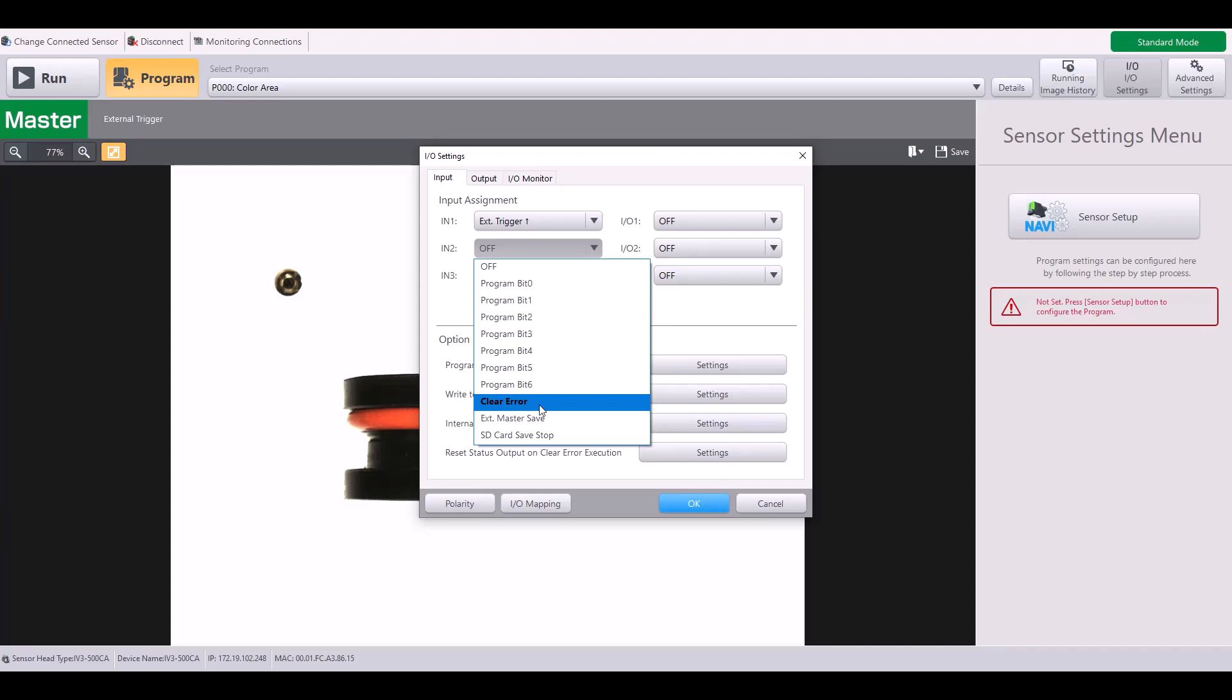The clear error input can also be used to reset the status output or your judgment value. You can also use it as an external master save, which means when you apply an input, it will take a new master image for your program.